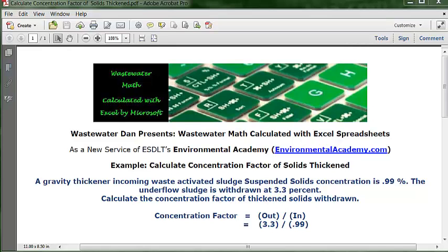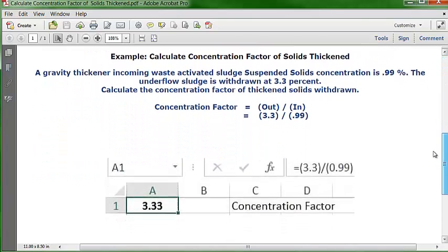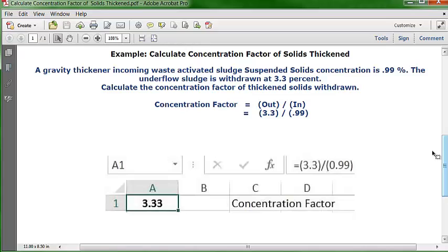The formula is: concentration factor equals the numeric value going out divided by the numeric value coming in. The number going out is the withdrawn underflow, and the number coming in is the incoming waste activated sludge suspended solids. They're both percentages, so we just use the numeric value without the percentage sign, divide one by the other, and get the answer. Let's see how this works in an Excel spreadsheet.